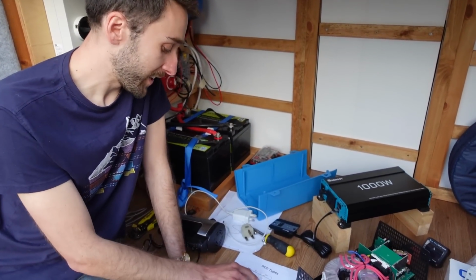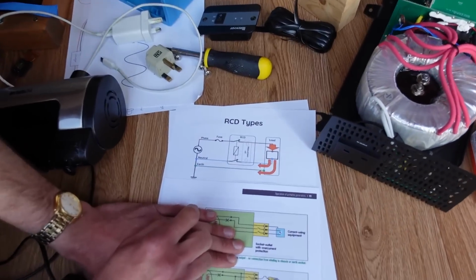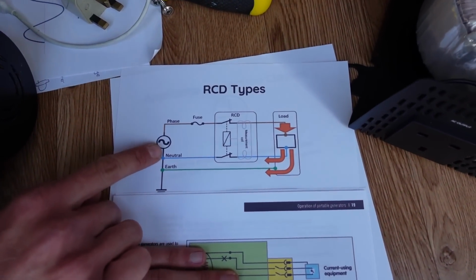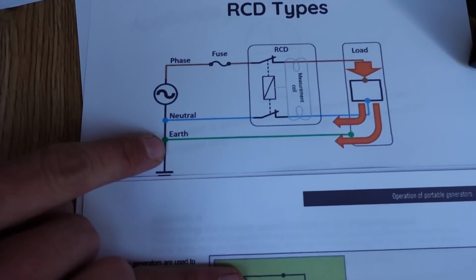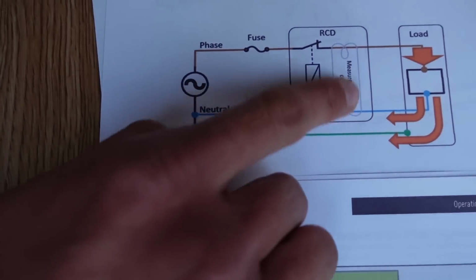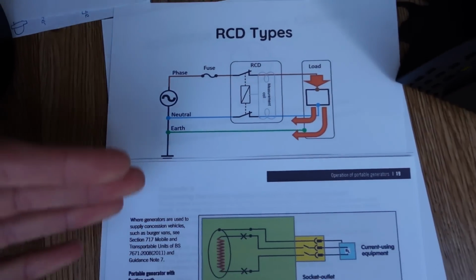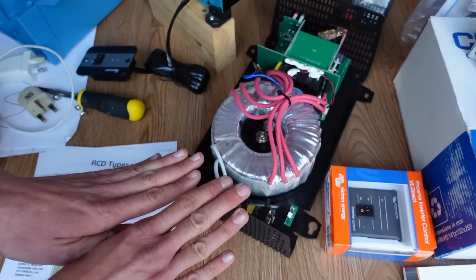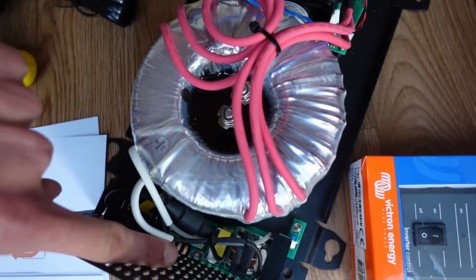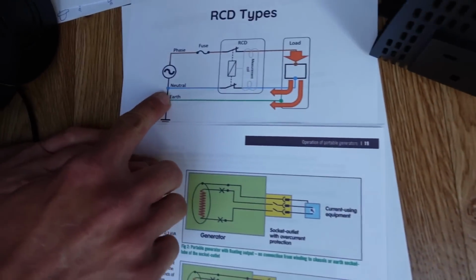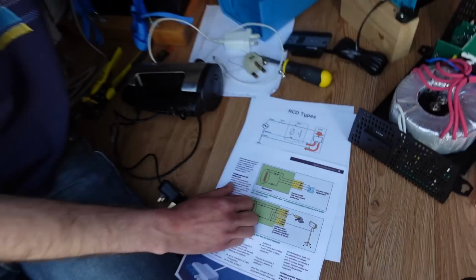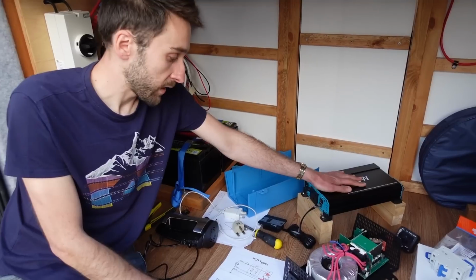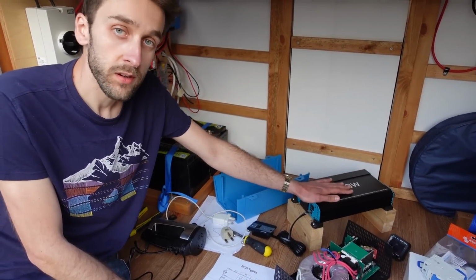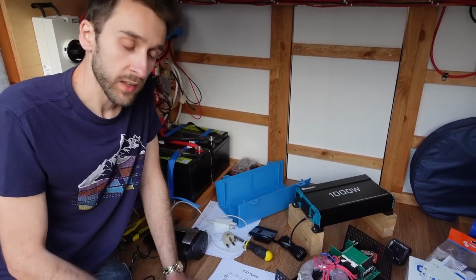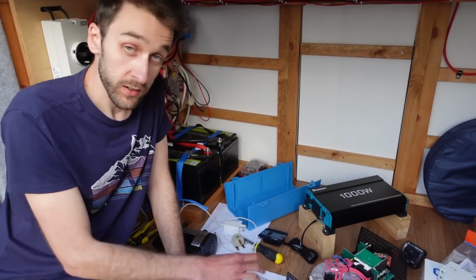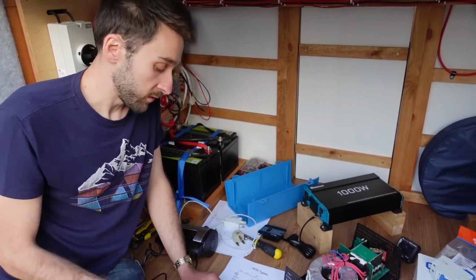So we want an RCD that's operational, and for that to work we also need what's called a bond between neutral and earth. You connect them together so the RCD can detect the imbalance. That's ultimately why we decided to go for the Victron inverter, because it has a little jumper you can move that sets up this bond so it'll work with an RCD, whereas the Renogy inverter doesn't have that functionality built in. If we wanted that bond with the Renogy, we'd have to do it separately in the consumer unit, and that's not something we wanted to do. We prefer something that's got the provision built in.